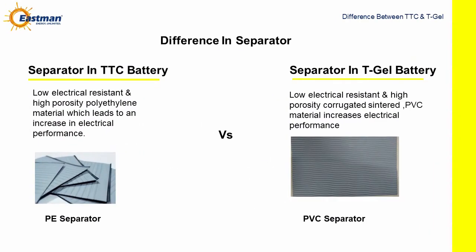Difference in separator. Separator in TTC battery is low electrical resistant and high porosity polyethylene material, which leads to an increase in electrical performance. While, separator in T-Gel battery is low electrical resistant and high porosity corrugated sintered PVC material, which also increases electrical performance.